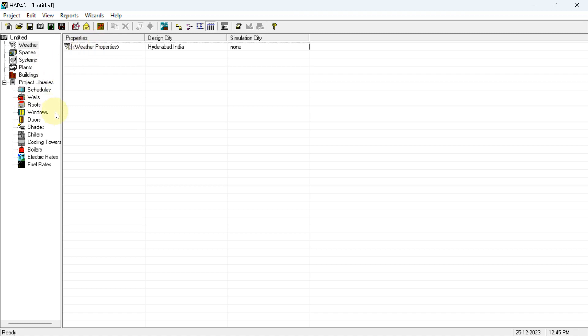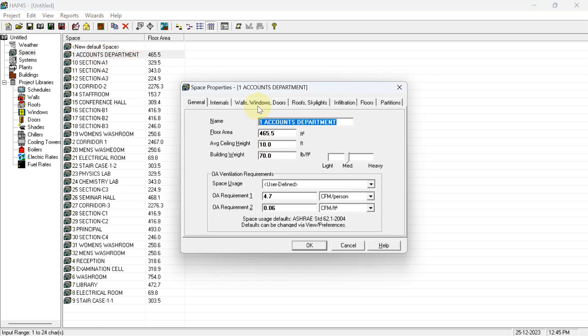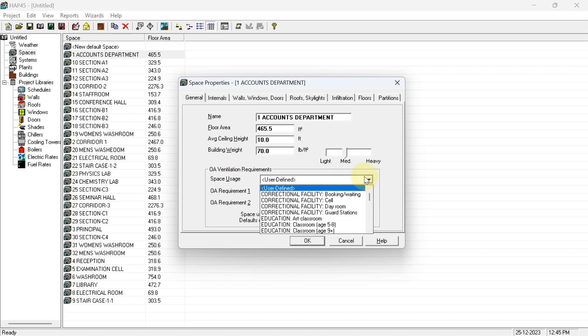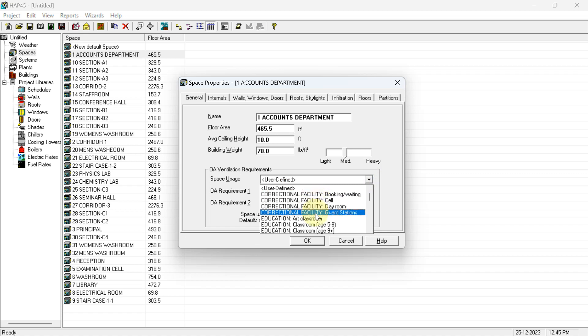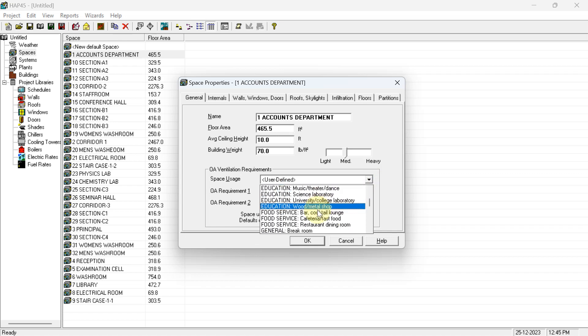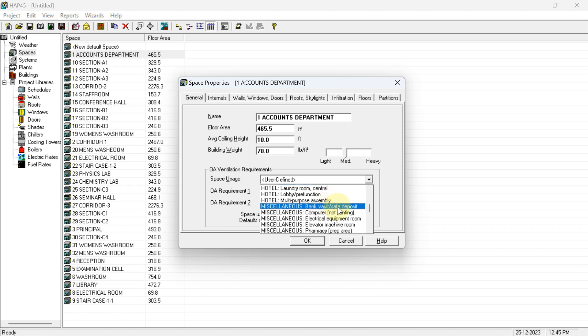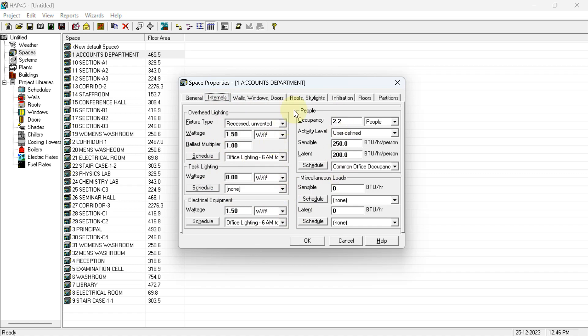Now come to the spaces section. Double-click on 'Account Department'. In the Outside Ventilation tab, you have to select the space type. By default Revit provides values like 4.7 cfm per person and 0.06 cfm per square foot. Select the room type closest to account department from the list — for example, under banking, 'Bank Vault and Safe Deposit' is a close match. Based on that selection, HAP will provide the cfm per person and cfm per square foot values.